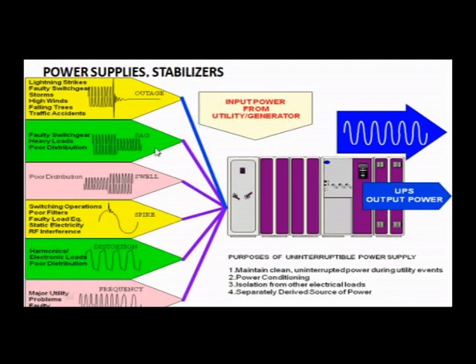Then there may be distortion in the waveform - harmonics from electronic loads and poor distribution. Finally, there may be a frequency change - 50 hertz is what is there, but there may be a change in frequency due to major utility problems. These are the things that need to be conditioned at the UPS output in spite of all these unwanted faults occurring at the input.